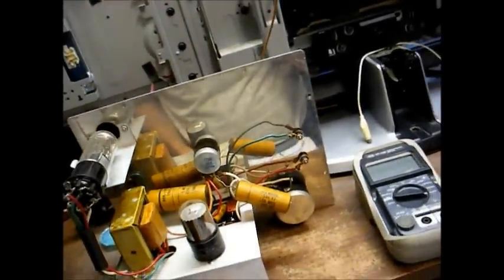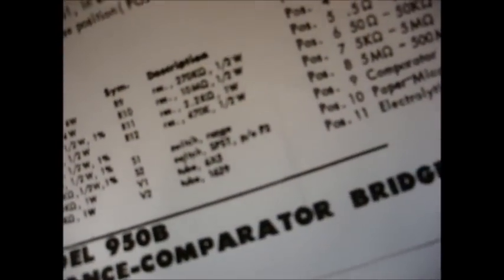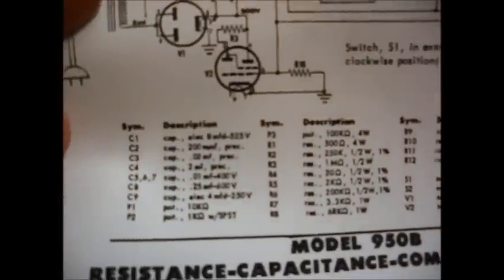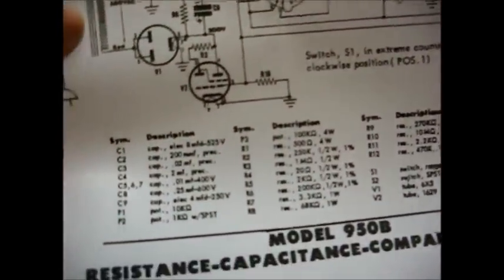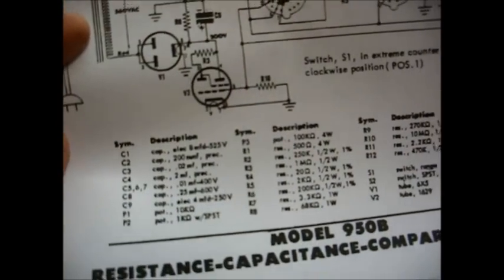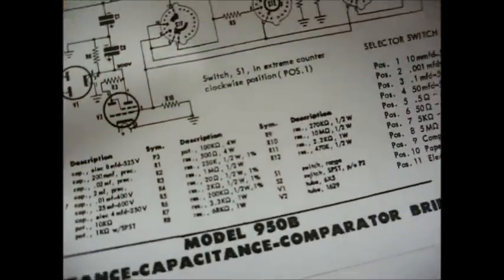Now, there are three capacitors in here that are worth mentioning. There is a 200 pF capacitor, a 0.02 microfarad capacitor, and a 2 microfarad capacitor that are in the bridge circuit. And all three of those are precision capacitors, which means I need to replace them with something with a very close tolerance, like 1% to 2%, in order to help ensure the accuracy of this piece of test equipment.